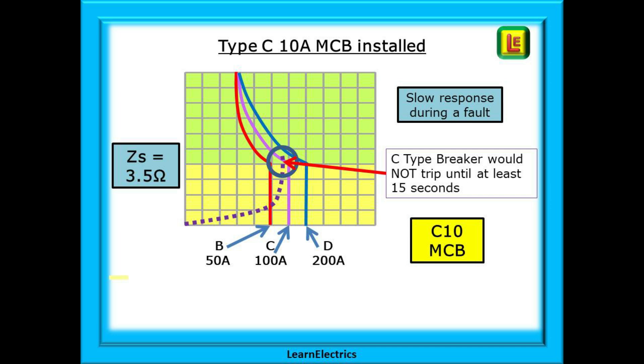The C type MCB is less sensitive. Because the ZS remains at 3.5 ohms, the device does not trip in 0.4 seconds as it should. In our example, it could be 10 to 15 seconds before it operates. The C type needs 100 amps to guarantee it trips in less than 0.4 seconds and we have now put the customer in danger during a genuine fault.